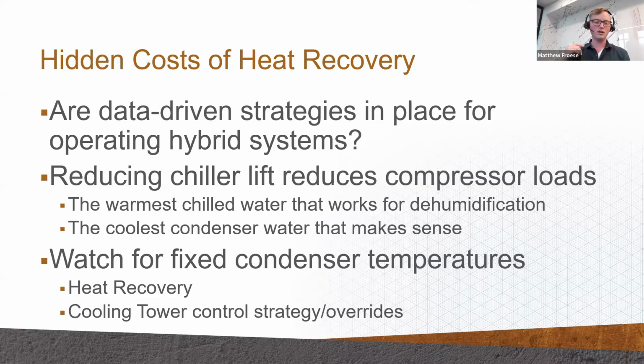And a lot of the times our sequences are preset. They're fixed to say, in this condition, we're going to run this equipment. It's going to control to this set point. And we maybe do some of that trim and respond set point adjustment, but those big choices are fixed ahead of time. And one of these places I think that can fall apart is when we're recovering heat from big chillers.